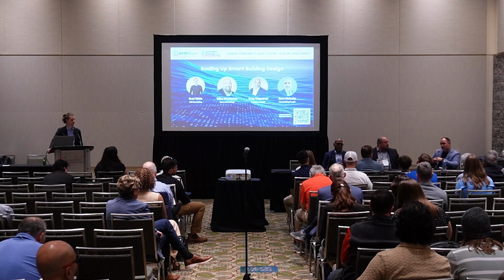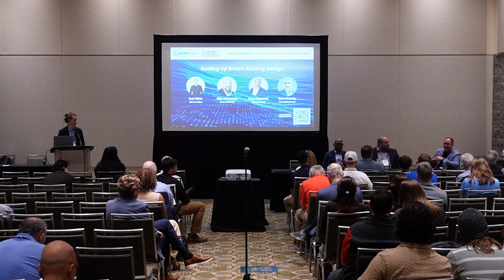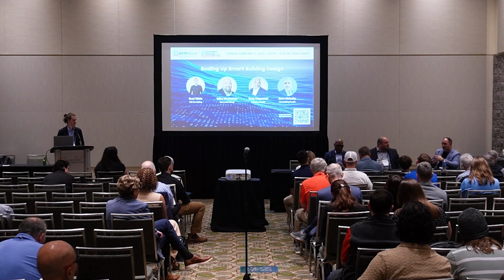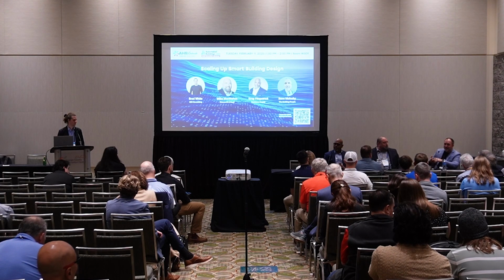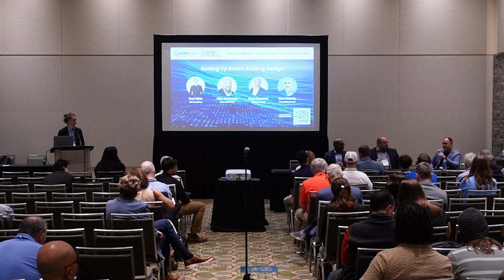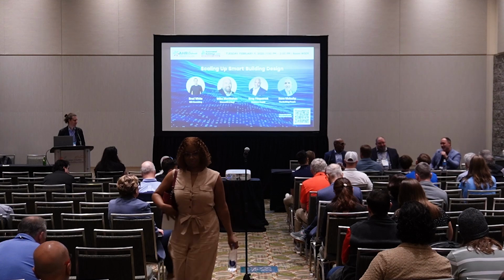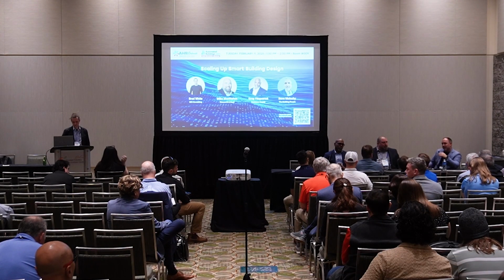I would even say, even for local accounts, yes, we've all come across those in the panel. They're written in Sharpie, great. But if you rotate your passwords on those and do a good job of that, and set up dedicated service accounts, that goes a long way. And the more IP devices that are getting added into that network, it could be the power meter, it could be a BACnet MSTP to IP router, all of those things have usernames and passwords, and I almost guarantee everyone I've come across is admin blank, or admin. It doesn't take much to get into these systems.